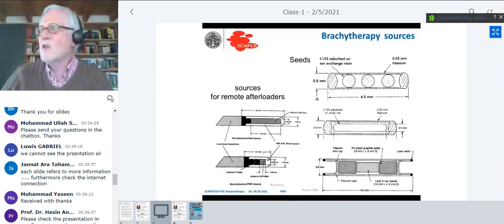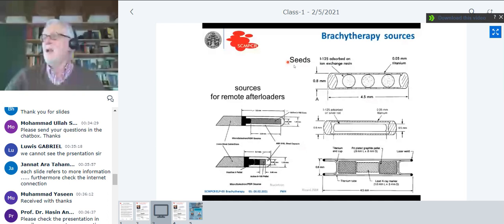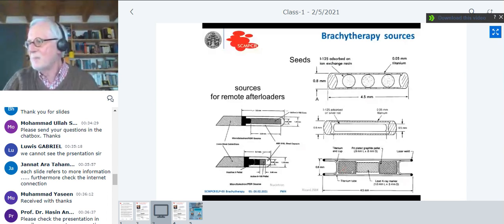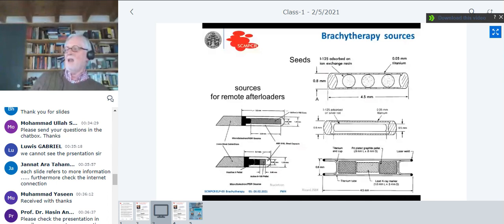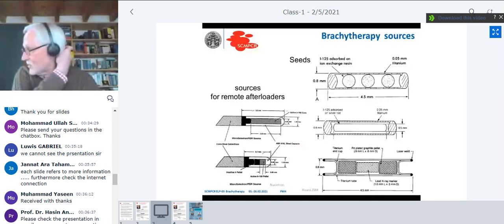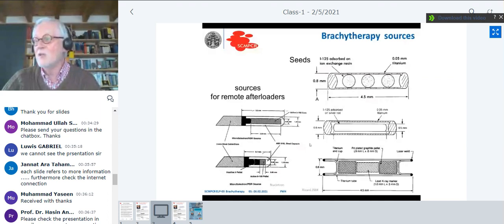Where we have a large variety of designs is in seeds. In this seed up here, the radioactive material, iodine-125, is absorbed on a resin on a sphere - little balls in here. Down here, it's absorbed on a silver rod in this source, and this source down here is not iodine, it's a palladium source - here you have a graphite pellet on which the palladium is absorbed, and you also have a lead marker. So these look very different, and that also has a large influence on the dose distribution, so you need to look at what the source looks like and select the correct dosimetric data for these sources. They are quite different.